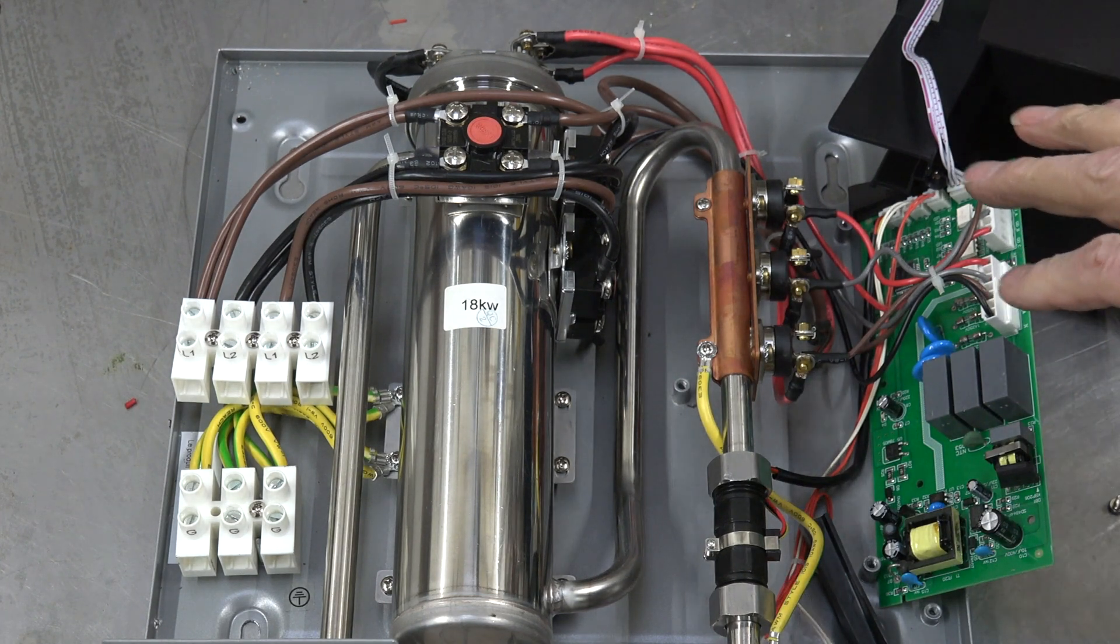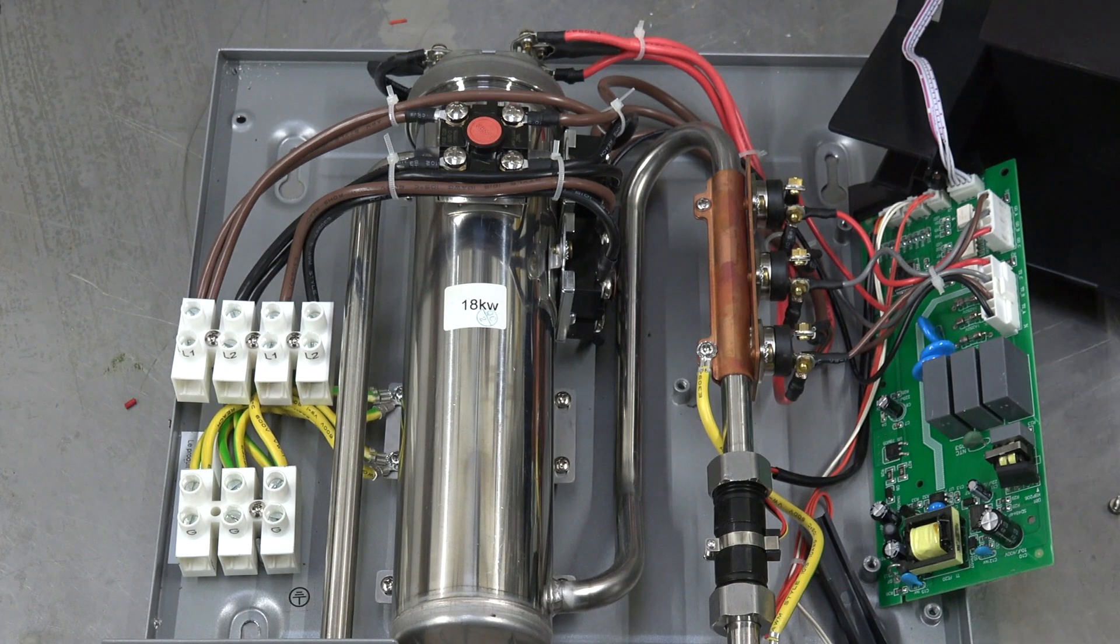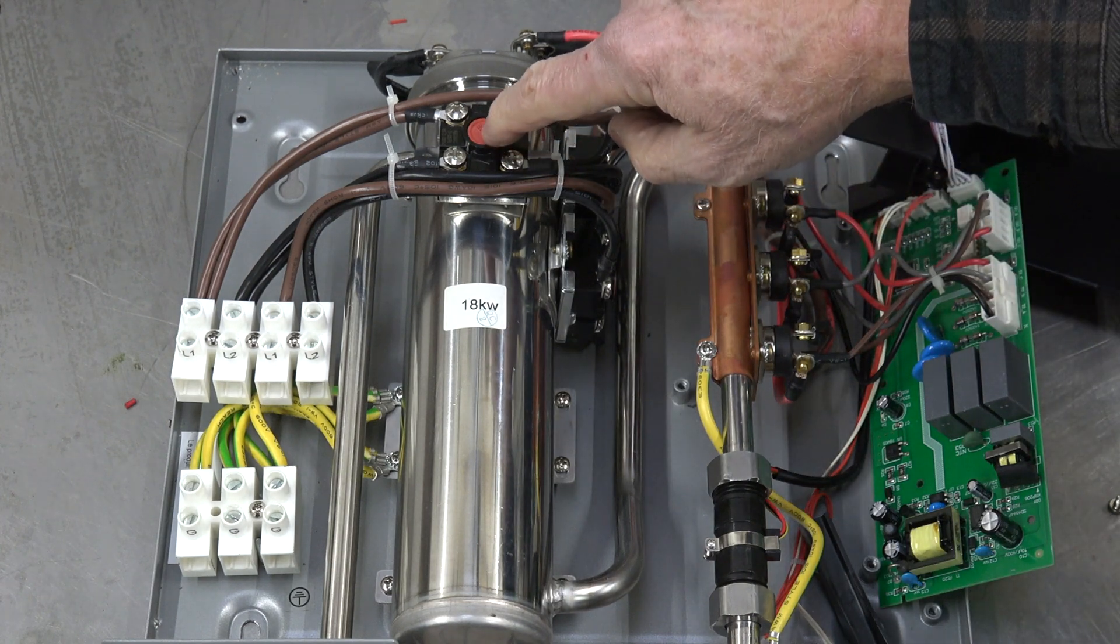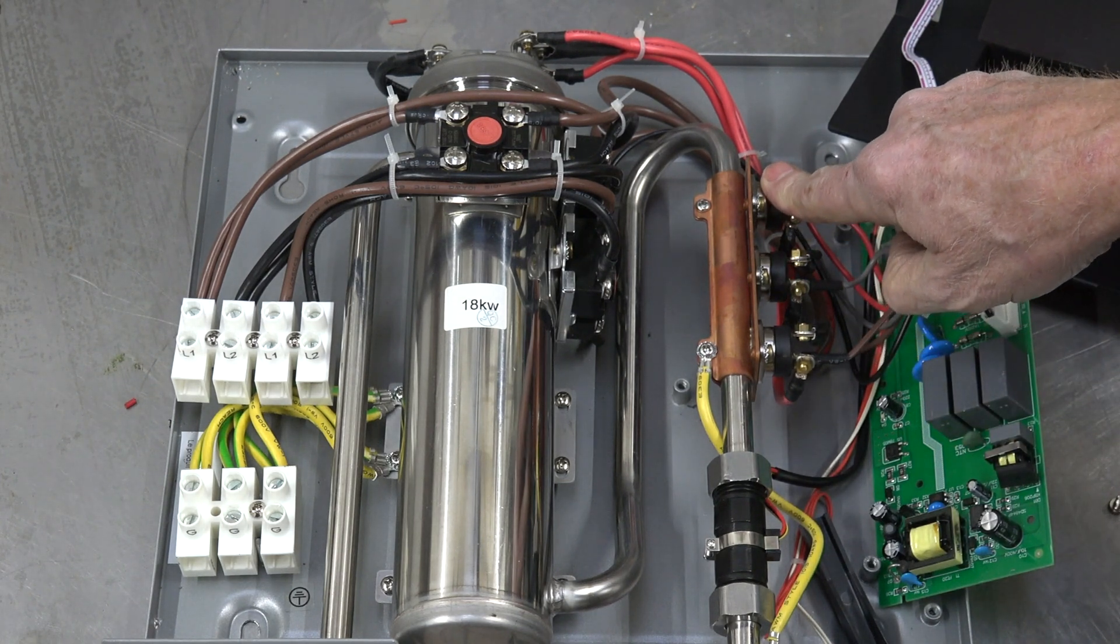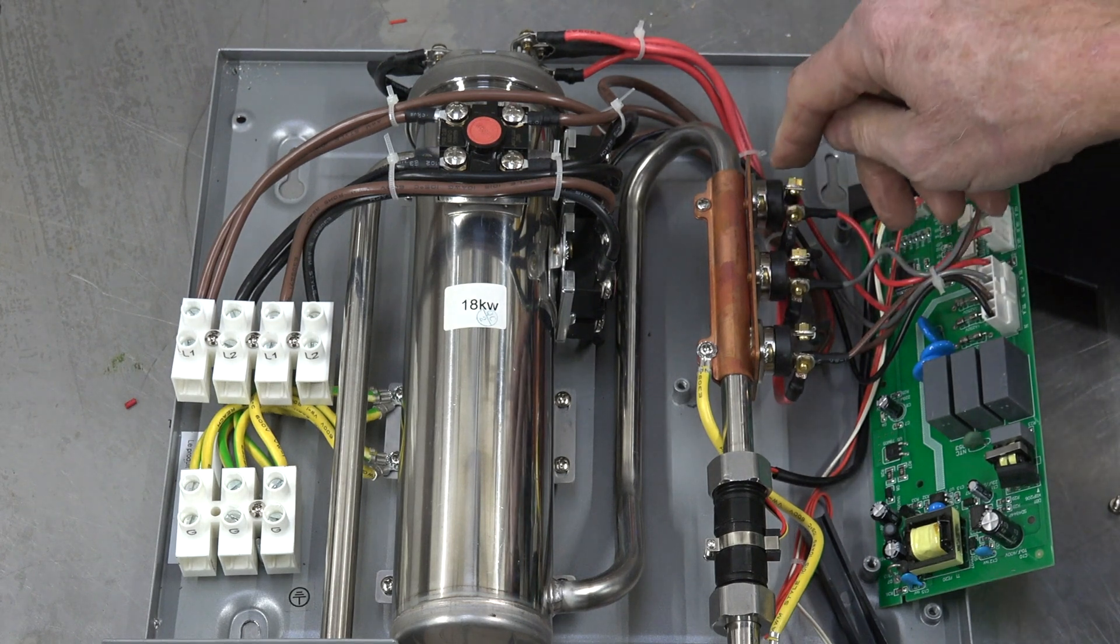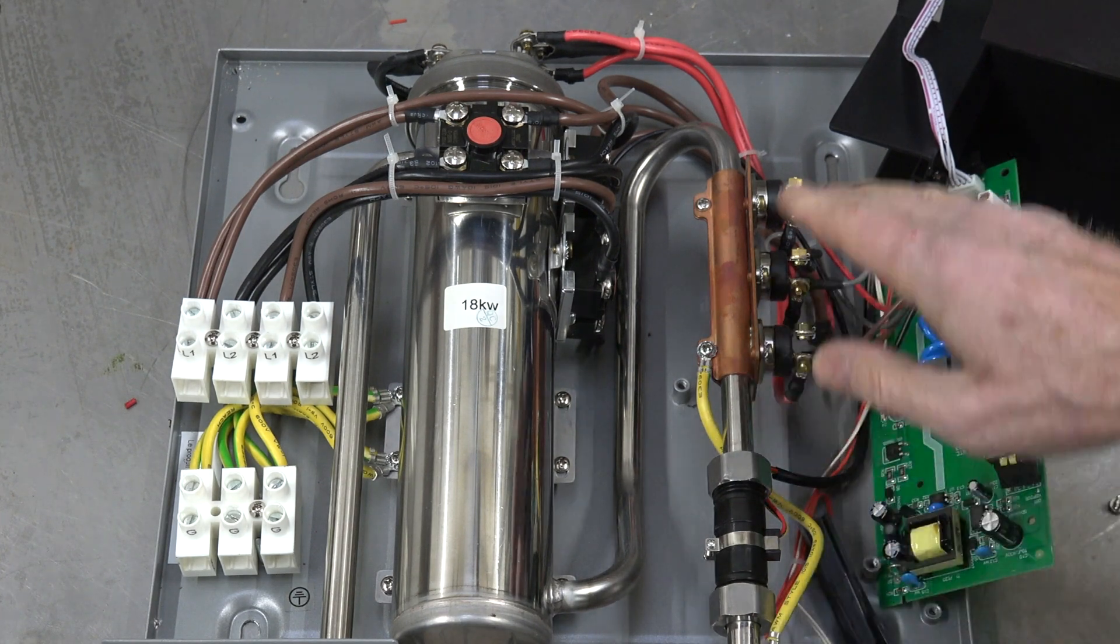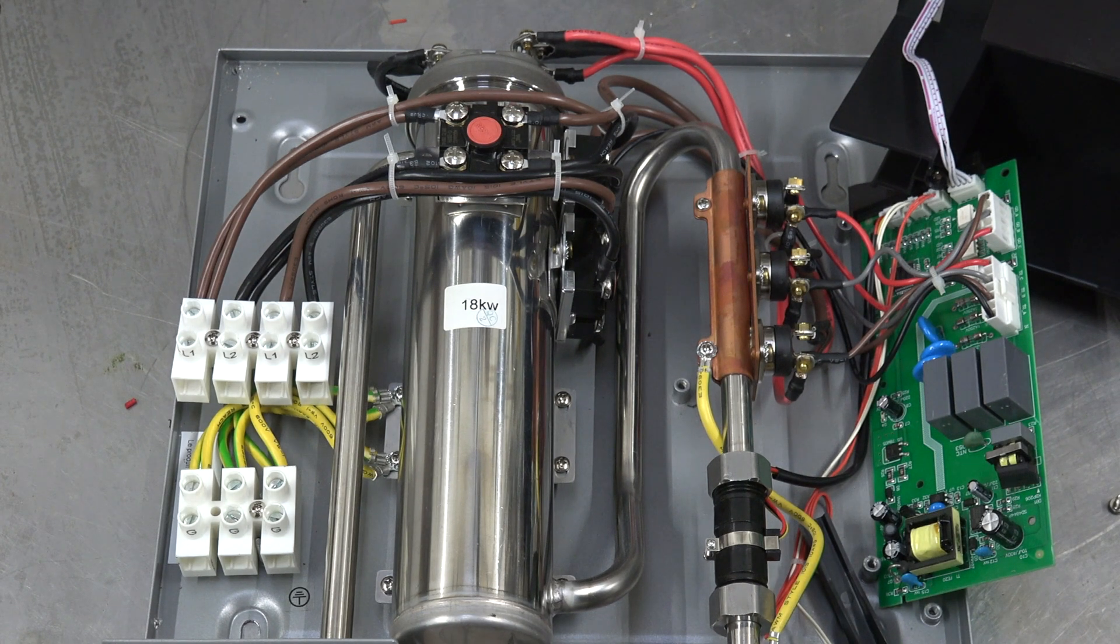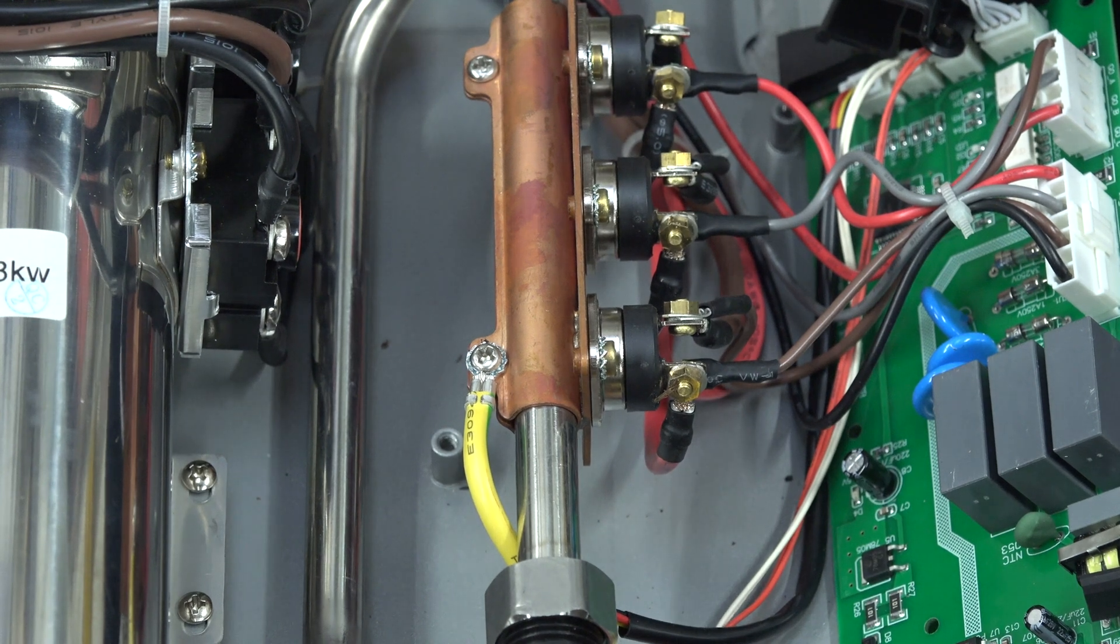So why did this thing do this? Now if one of these switches had stuck on, that would do it, because if one of the control switches leaves an element on and it's physically stuck on, then the flow switch is not going to shut it off. So let's do a little bit of troubleshooting on this thing to see if we can figure out what happened.